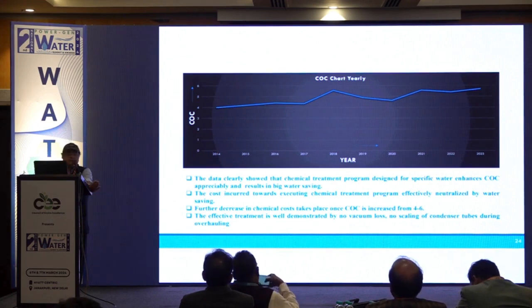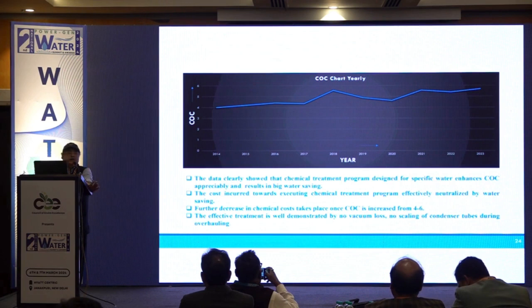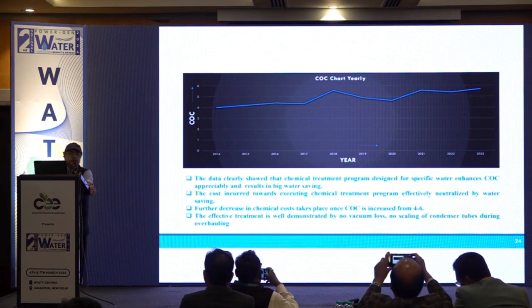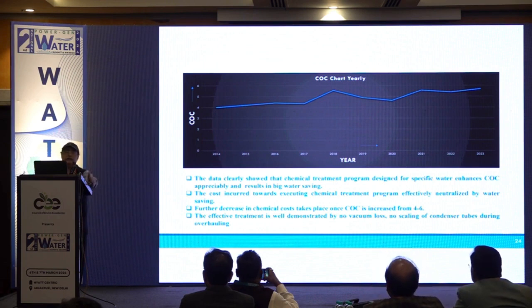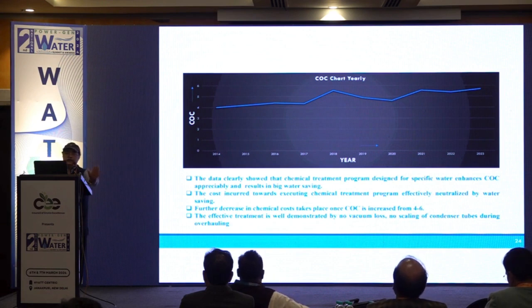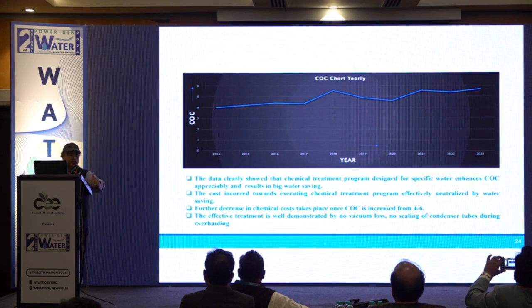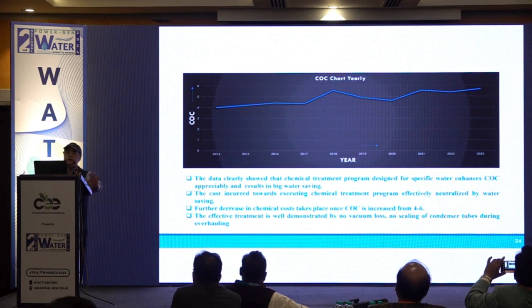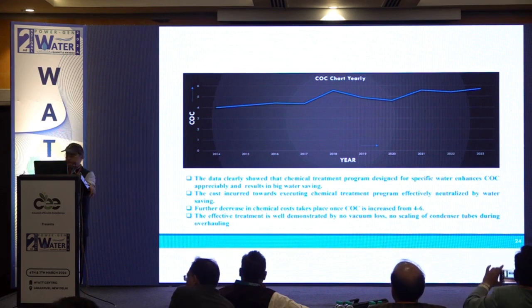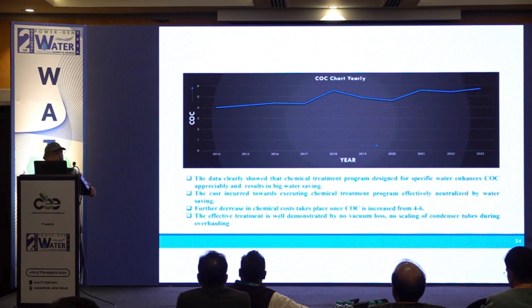This data clearly shows that a chemical treatment program designed for specific water enhances the COC appreciably and results in big water and cost savings, but it has to be designed properly, otherwise we cannot achieve those results. There may be more chemical consumption, which may lead to other problems like scaling, rather than solving our issues. So it must be designed over a considerable period of time, keeping seasonal impact in mind, only then can we design that particular treatment.